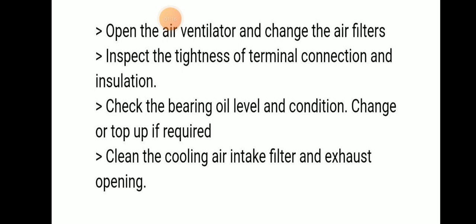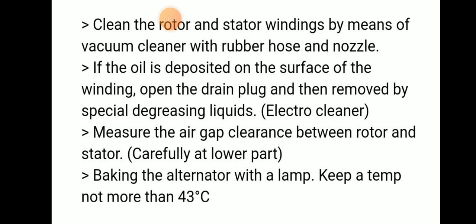Then we have to clean the cooling air intake filter and exhaust opening. What I mentioned is the cooling air intake filter, there may be some choking, and we also have to clean it. Then clean the rotor and stator windings by means of a vacuum cleaner with rubber hose and nozzle. There will be some dust on the rotor and stator windings, so we can clean it using a vacuum cleaner with rubber hose and nozzle.